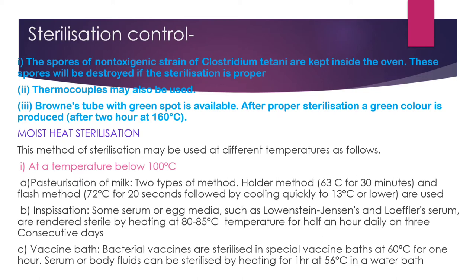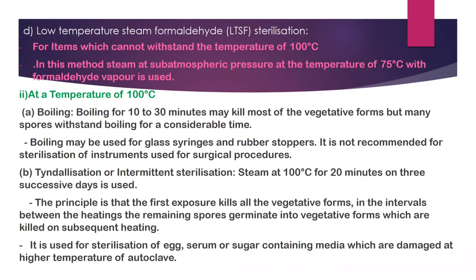Low temperature steam formaldehyde sterilization is used for items which cannot withstand temperatures of 100°C. In this method, steam at sub-atmospheric pressure at 75°C combined with formaldehyde vapor is used.